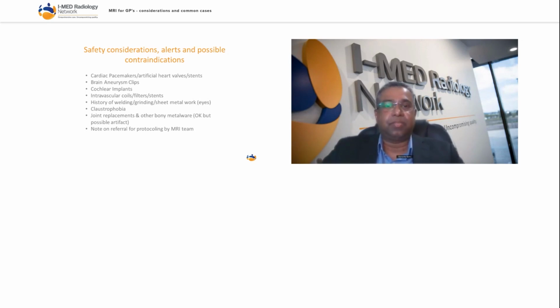Some of the older pacemakers are deemed MRI unsafe, but the newer pacemakers are what we call MRI conditional. That is, in certain situations and in certain MR environments, they may be safe. So some of the new pacemakers may be safe with a 1.5 Tesla MRI scanner, whereas they may not be safe with a 3 Tesla scanner. So if you know any information about the brand, the type of the pacemaker, or if there are MRI safety aspects, then it's important to let us know.